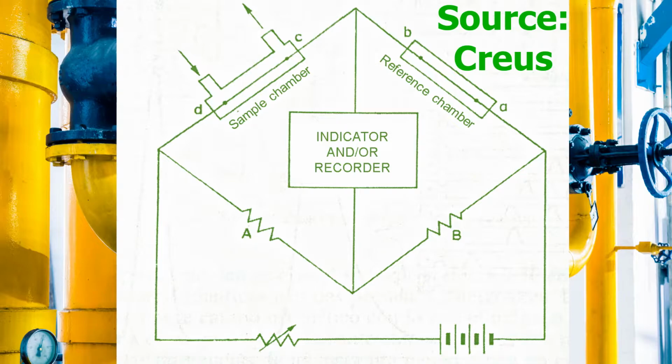The gas is sucked in with a pump and passes into the cell. This contains a resistance wire electrically heated and maintained at a temperature slightly higher than that of the walls. With a good design and limiting the temperature rise of the hot wire, heat transmission by convection and radiation is negligible. Consequently, the resistance of the central wire is inversely proportional to the conductivity of the gas that surrounds it. Variations in gas and instrument temperature are compensated for by means of an identical closed thermal conductivity measurement cell containing air of known composition, or two sample cells and two reference cells.